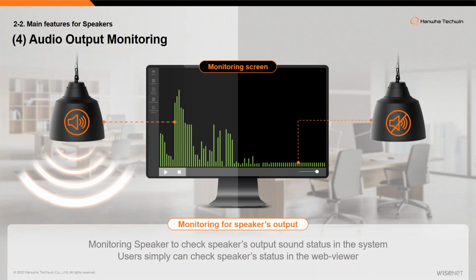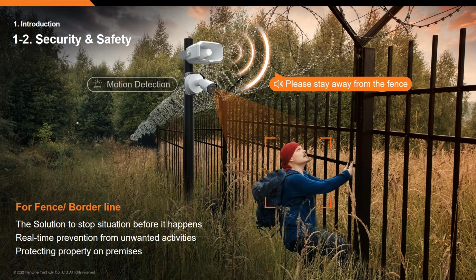Yeah, so here you can see that in the monitoring interface, you can monitor the output level from the speaker. If there is no output, then you know the speaker is down. You can also have it integrated with the CCTV system. So if the camera detects an object based on analytics, it can send a command, or through the VMS, make an announcement on the speaker. Or you can also do dry contact, which means from the camera you can plug a dry contact to the speaker, and the speaker will also make the announcement based on the alarm input.